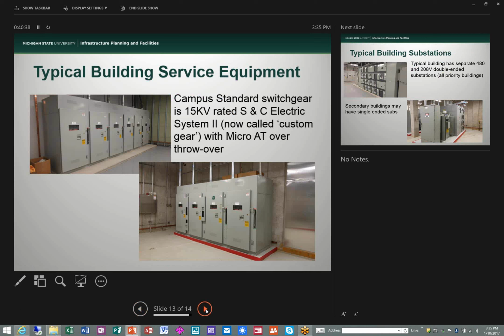So here on this slide, we'll take that lower right-hand photograph. The 2 switches on the left are the incoming switches, and one is normally open and the other one is normally closed. Now we put an orange dot in the window of the circuit that building is preferred to. And the nice thing about the S&C equipment, it's the only manufacturer we can close couple tie, cross-closed switches, without any issues.